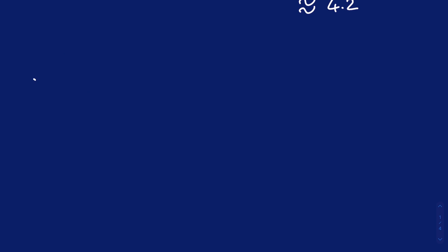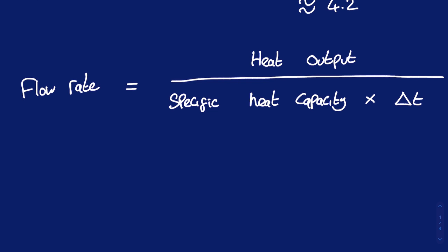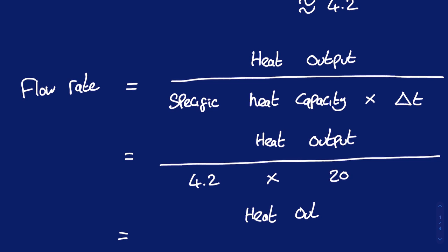Here's how these relate to each other. The industry standard is to have a delta T of 20 degrees Celsius, so this formula simplifies down to heat output divided by 84. Clearly, heat output from the radiator is a key factor when calculating flow rate.